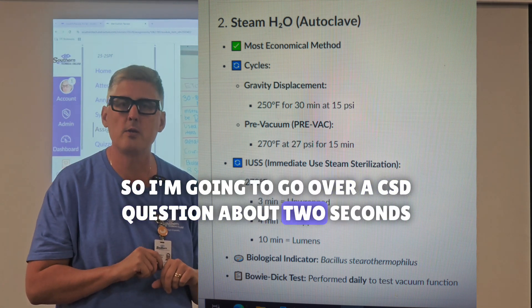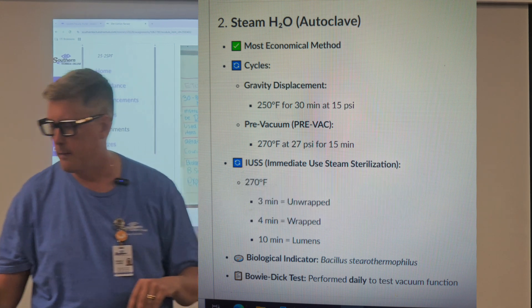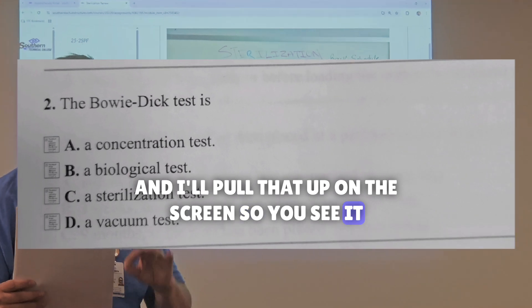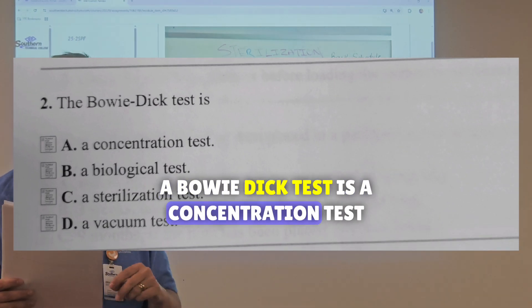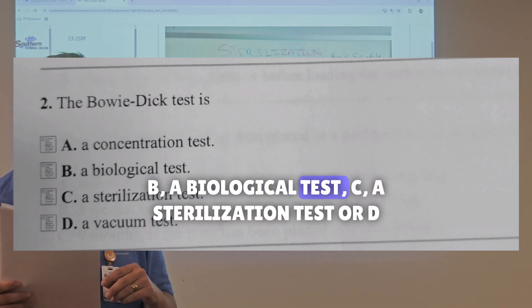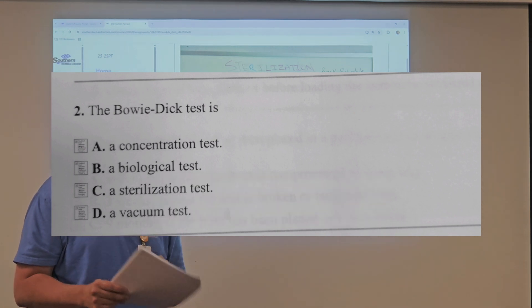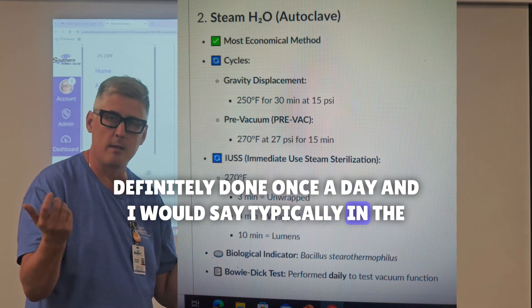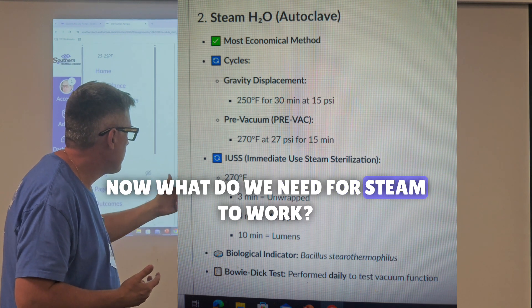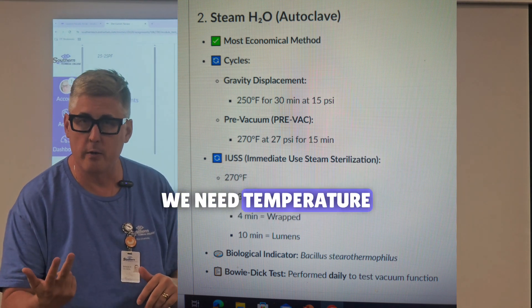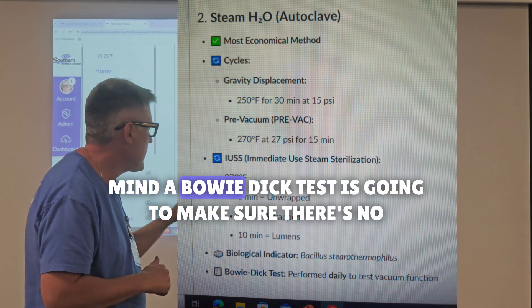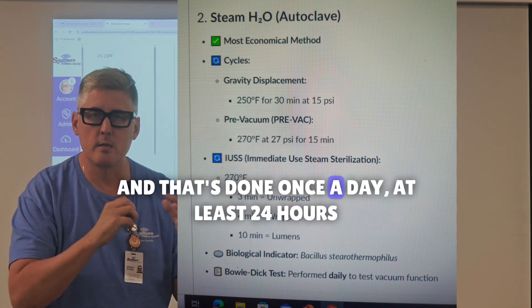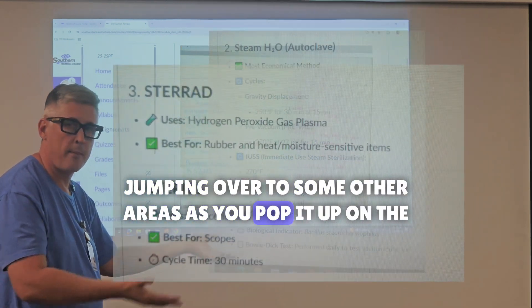Question number two: a Bowie-Dick test is — A, a concentration test; B, a biological test; C, a sterilization test; or D, a vacuum test? The Bowie-Dick test is done once a day, typically at the beginning of the day. What does steam need to work? Temperature, time, and pressure. The Bowie-Dick test ensures there are no leakages in the system and checks the pressure within the autoclave. That's done once a day, at least every 24 hours. The answer is D, a vacuum test.